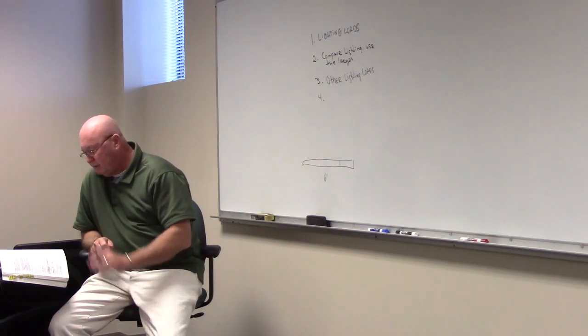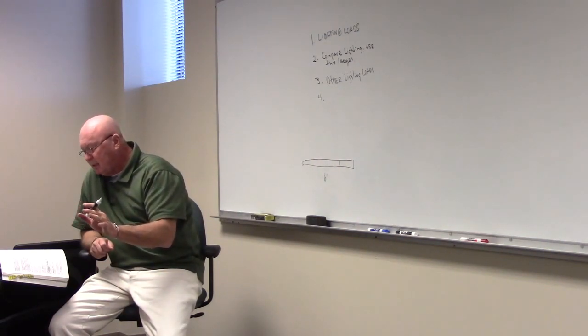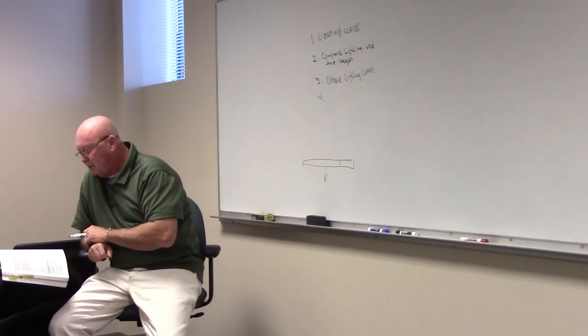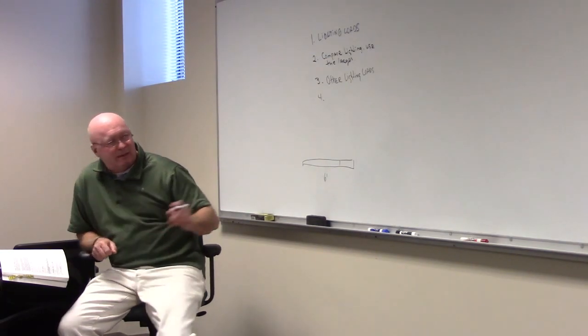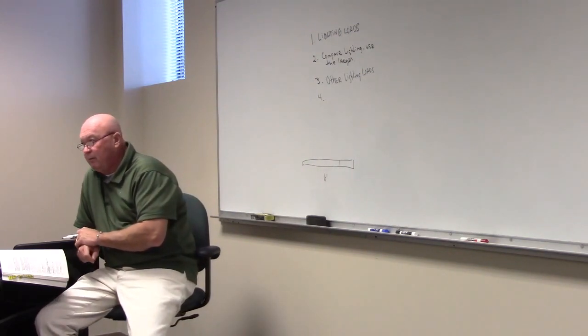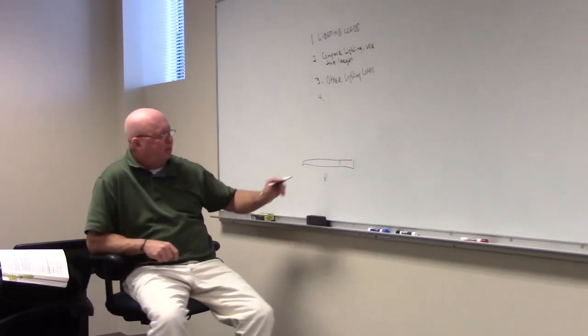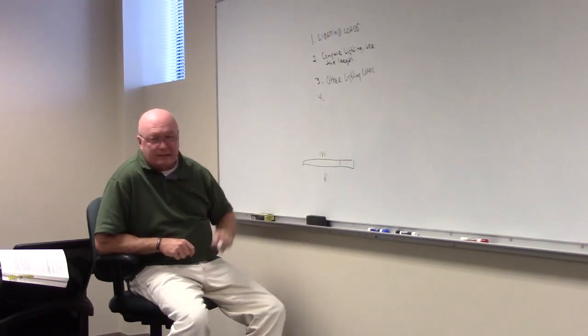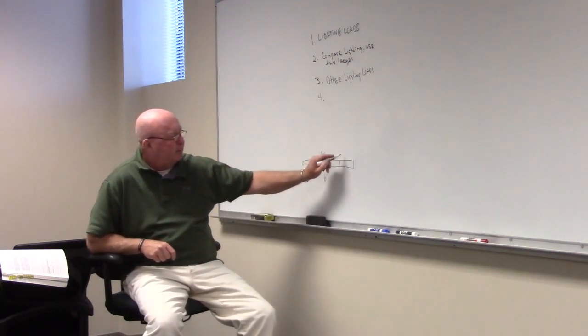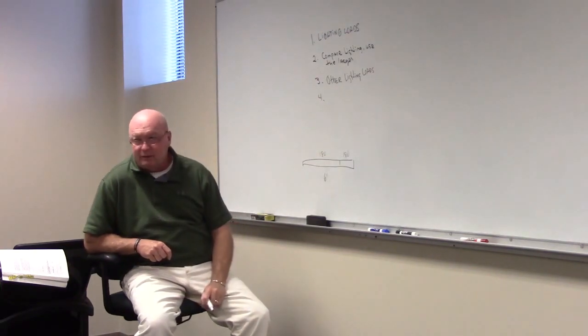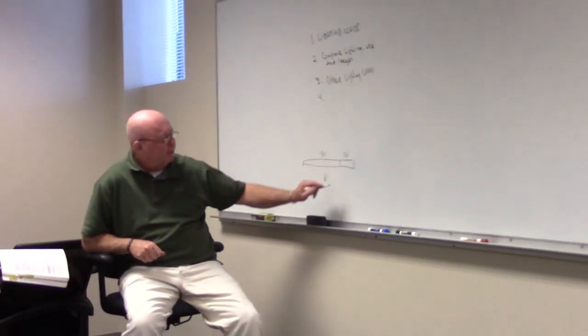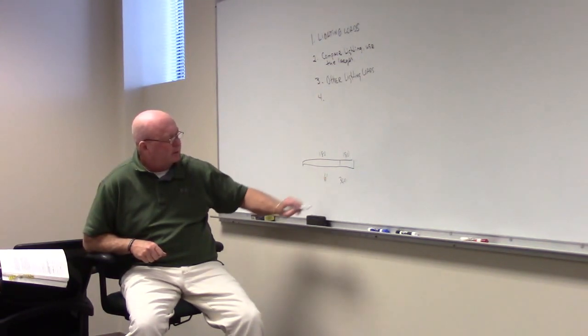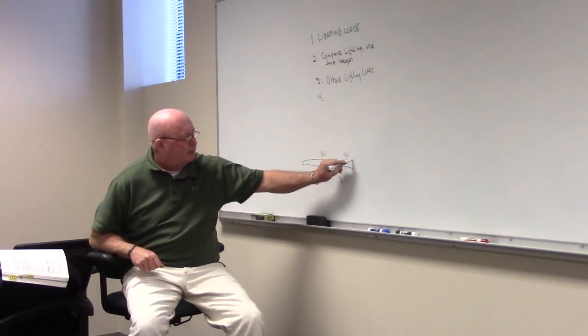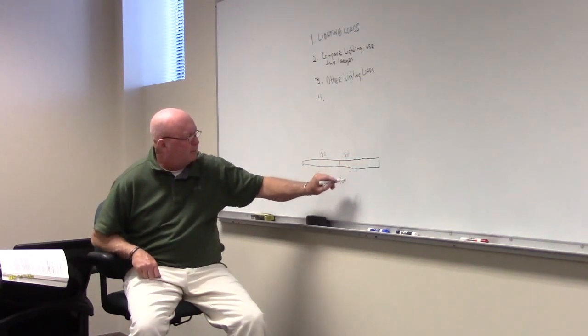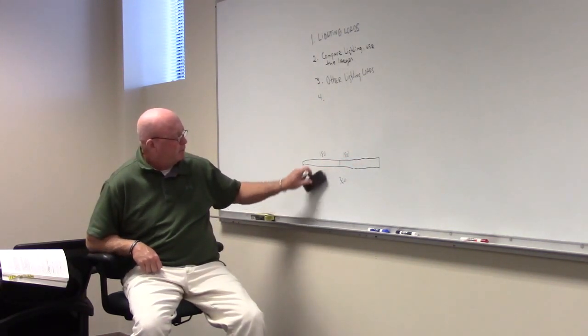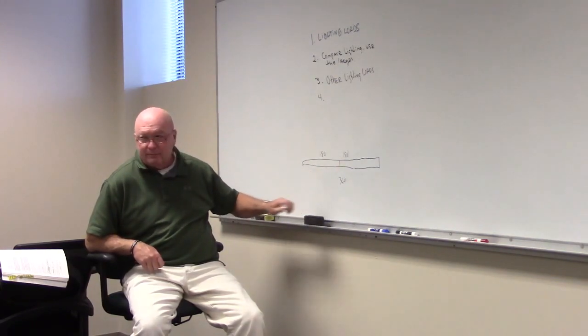Where appliances are, well, let's say the outlets are unlikely to be simultaneous. How many volt amps is this strip? Should be 360. 360. Very good, James. Well, there's 180 for this, and because it's a foot over, not a major fraction, it just says fraction over, so it's 180 for that. You get a total of 360. If it would have been 8 foot long, what would our volt amps have been? Same thing. Same thing. Yeah.